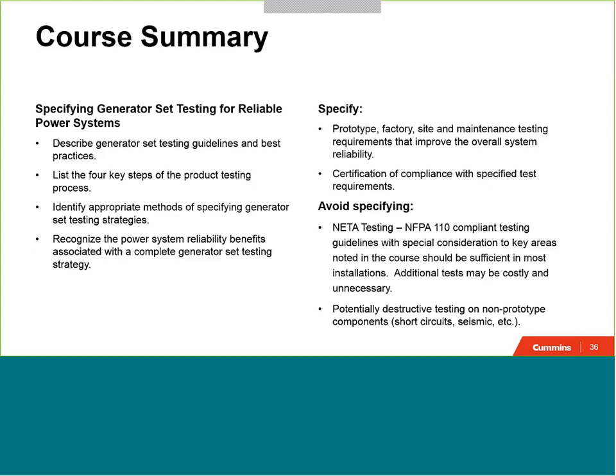We'd like to recommend that you avoid unnecessary testing, and I picked on NETA here as an example. There are testing strategies that we see adopted sometimes that go kind of the far end of things, where we're seeing tests that are either potentially destructive or they're tests that have already been conducted by the manufacturer, and a repeat of them in the field or on site is only driving additional costs in the product. So be aware of unnecessary test requirements and ensure that you're providing only what's really critical to your particular project.